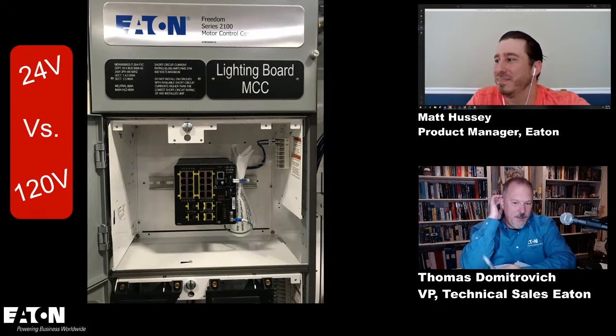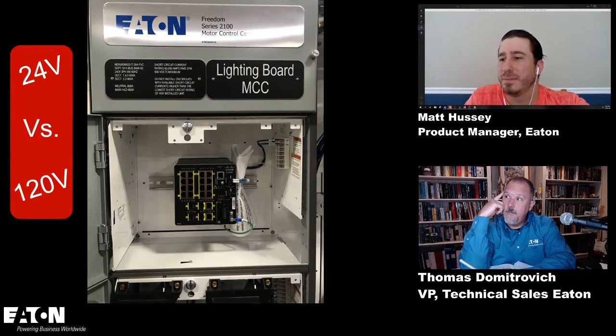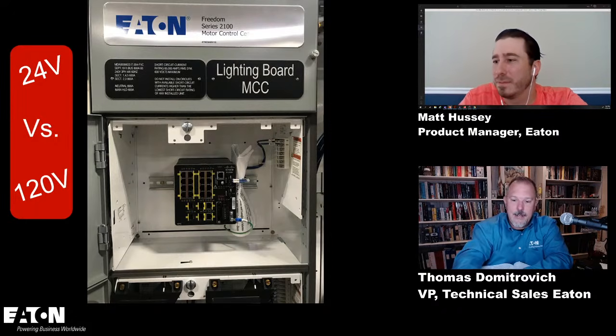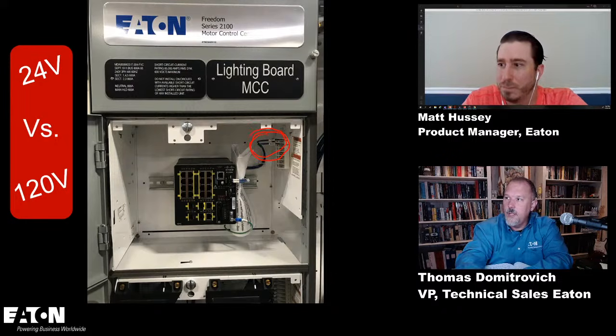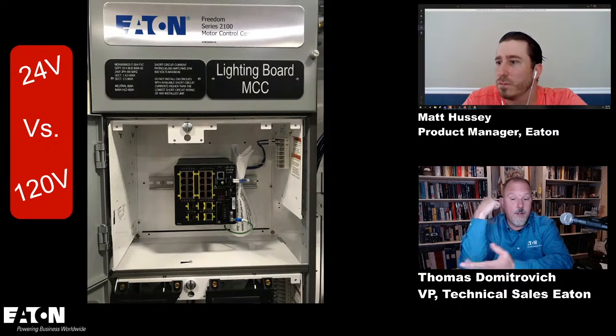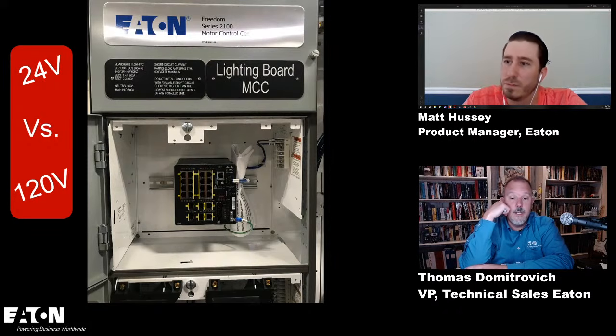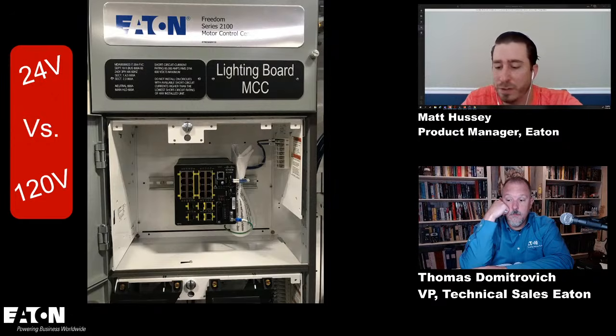Yeah. Now, this bucket here that we're showing, you pointed it out when you sent me that image, but up here it's connected to control power, just 24 volts, and there's no power in here. So can I just take a bucket like that and put DIN rail in it, and if I wanted to run Ethernet, or put a little hub in there or something like that? Yeah, that's basically a relay compartment. So if anything, it might validate that the devices have been appropriately rated. We're not invalidating any of their installation spacings and whatnot. But yeah, it's completely usable space for a lot of different applications.